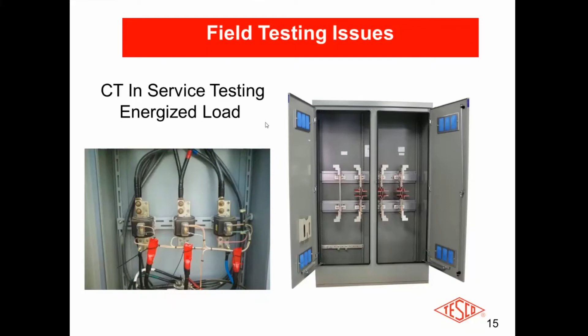But if one of those is reversed, and I've seen it multiple times, we've gone to a site that had never been tested before to find it was actually reversed from the day it was installed. This could be 10 or 15 years since they did the test. So they had identified a very low bill problem, which resulted in 66% less revenue for that installation. It's a big problem if you find these, and that's the reason we do these tests. We're trying to ensure the customer is not underbilled or overbilled. Nobody wants either of those things.